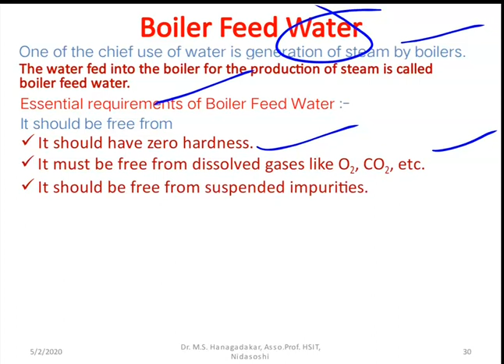Second, the water must be free from dissolved impurities or dissolved gases like oxygen, carbon dioxide, etc., which cause boiler corrosion. The boiler feed water must be free from suspended impurities. Boiler feed water should be free from dissolved salts and alkalinity. Boiler feed water should be free from turbidity and oil. Boiler feed water must be free from hardness-causing and scale-forming constituents like calcium and magnesium salts. So these are some important parameters essential in water before feeding into the boiler.